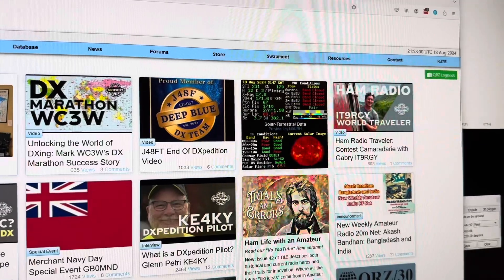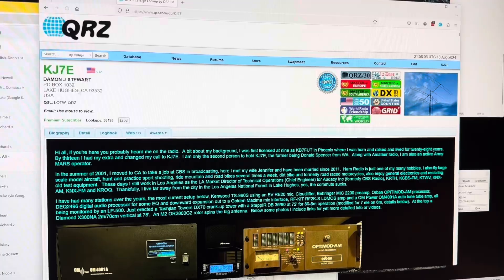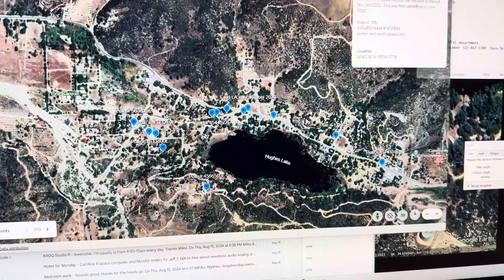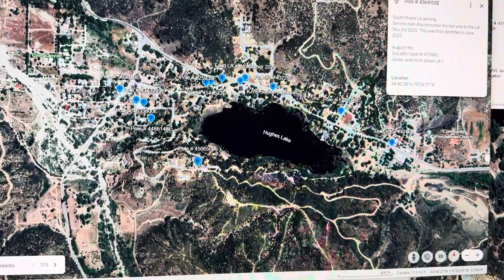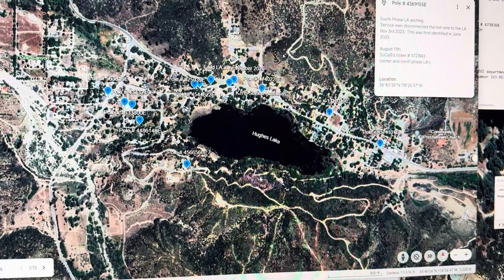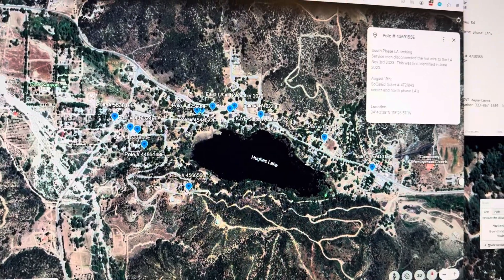I have an interactive map here. Let's go to my QRZ page and scroll down. Here's a map - and this is not even a hundred percent up to date, I've got to add to it. Here's my list of various power poles and dates that I've had to report that have been arcing. These are all the various power poles that have had bad lightning arresters. Every single case has been a bad lightning arrester. These lightning arresters are garbage.